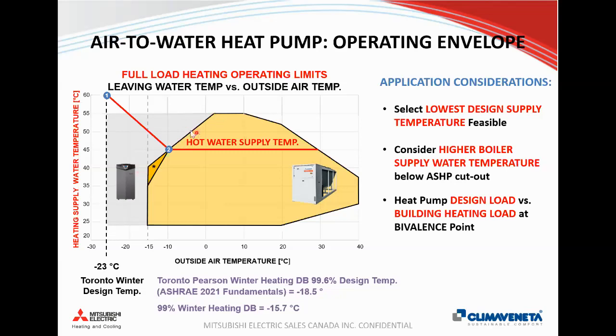So all the units in this class of heat pumps can typically give you around 50 degrees Celsius at about -5, and about 45 degrees Celsius down at -10. But at the fixed cutout temperature of -15, these machines give you low temperature heat, maybe 35 or 40 degrees. With new A2L refrigerants, these will improve.